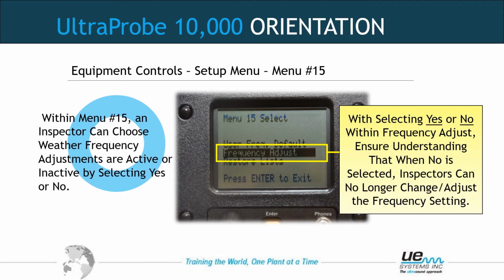Now we can lock out the frequency. So frequency adjust is either yes or no once you enter into here by pushing the sensitivity knob. Yes, we can adjust the frequency. No, we cannot adjust the frequency. The only time I think you would use this might be if you have someone new that you're training on a bearing route, for instance, and you have only a certain amount of time to train them. You've baselined everything already.